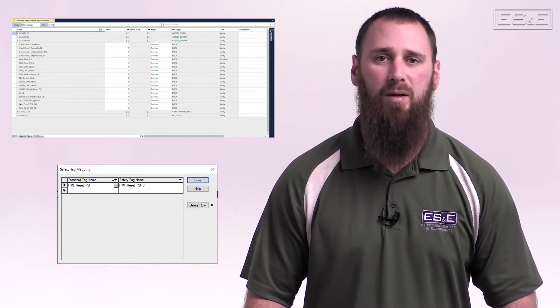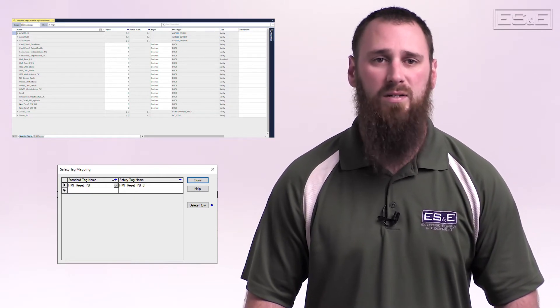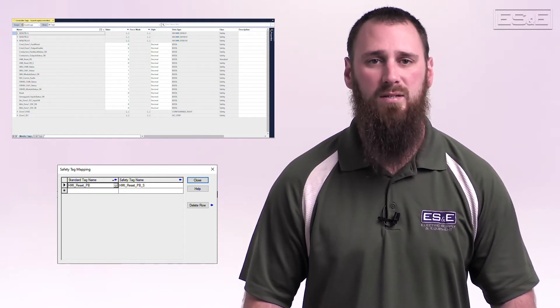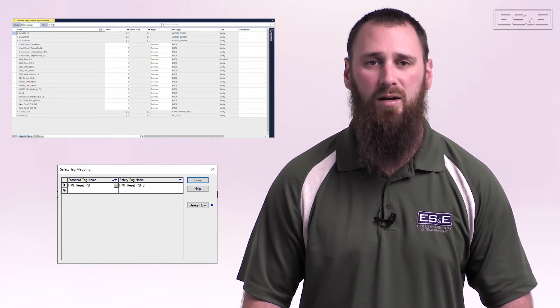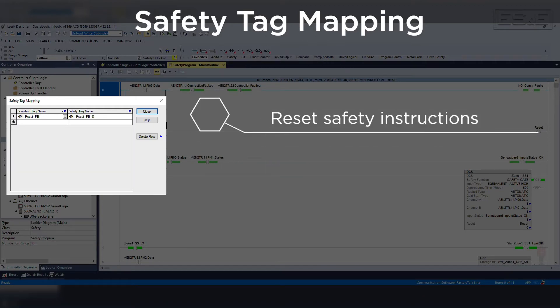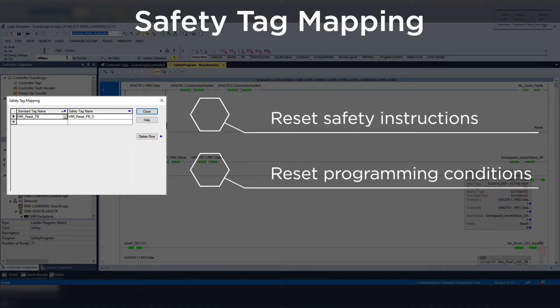This map allows you to write data from the standard class tags into the safety task, very similar to how the safety task scans safety class tags and IO. The function is essential when attempting to reset safety instructions, such as an e-stop that has a manual reset function, or programming conditions such as machine sequence step to disable a piece of equipment from moving.